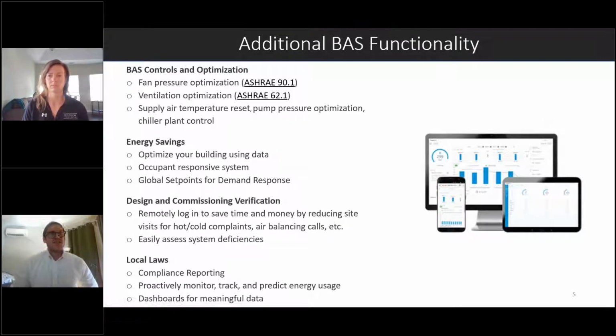So here's some additional functionality you can get out of a building automation system. There are certain energy optimization strategies that require networking controllers together to implement. Something like fan pressure optimization relies on an air handling unit working in unison with your VAV boxes, communicating with one another to ultimately reduce the amount of fan usage at your air handling unit.